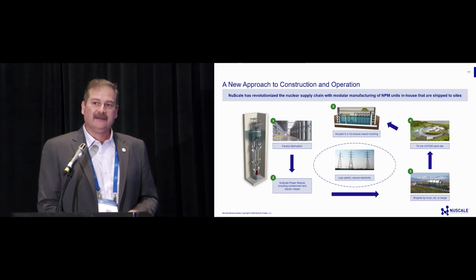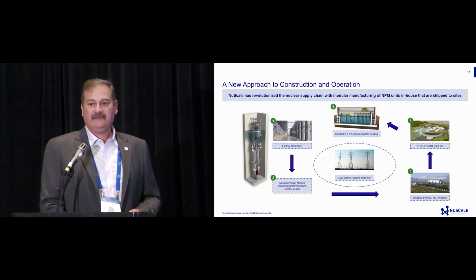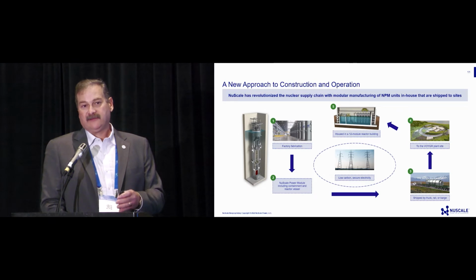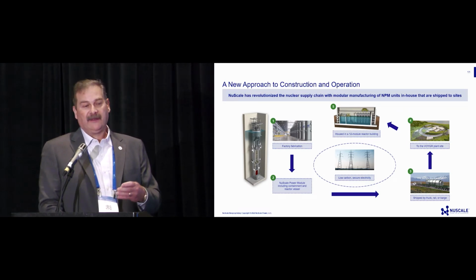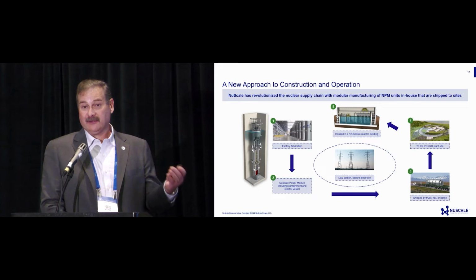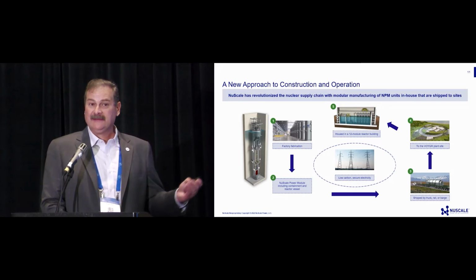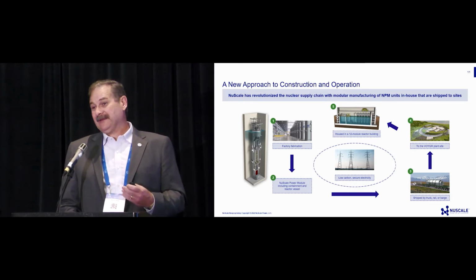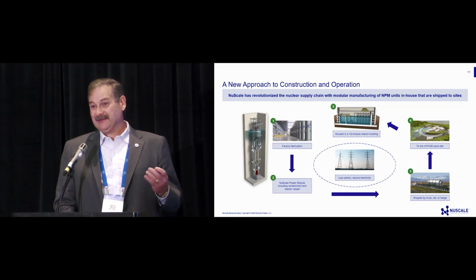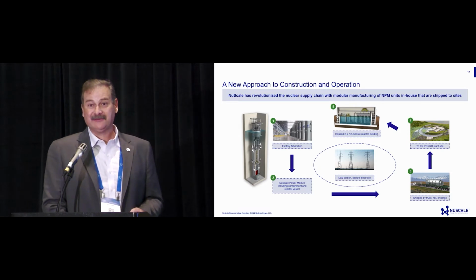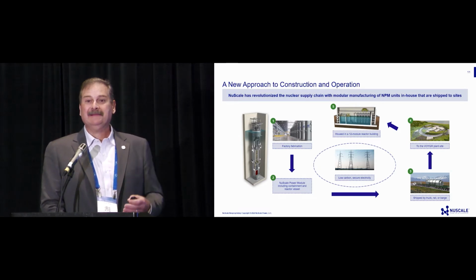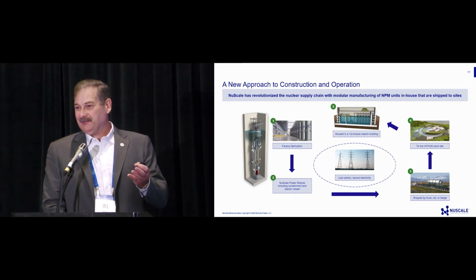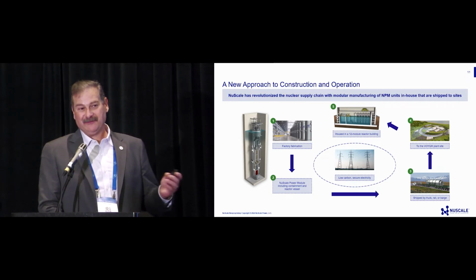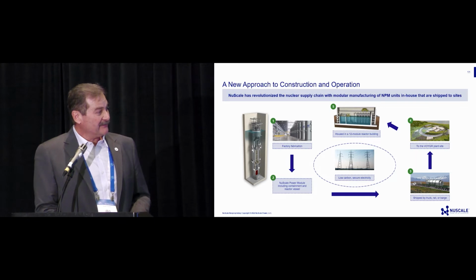And we had some unique challenges for the UAMPS design, in that they wanted to have the steam out of the steam generator cooled by air-cooled condensers, vice a circulating or evaporative water system, because the plant was in an arid area and the availability of water may be in question, and just using water for cooling and evaporating it didn't seem very environmentally conscious to us either. So we pursued that. That jumped up the cost a little bit to have a different cooling system, and so the 6-module design worked out a little bit better for them.